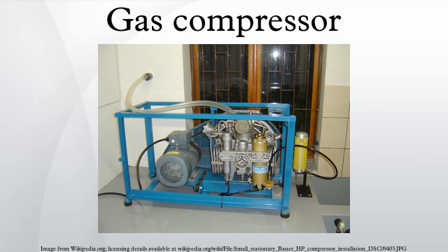They can be either stationary or portable, can be single or multi-staged, and can be driven by electric motors or internal combustion engines. Dry vane machines are used at relatively low pressures for bulk material movement, while oil-injected machines have the necessary volumetric efficiency to achieve pressures up to about 13 bar in a single stage.